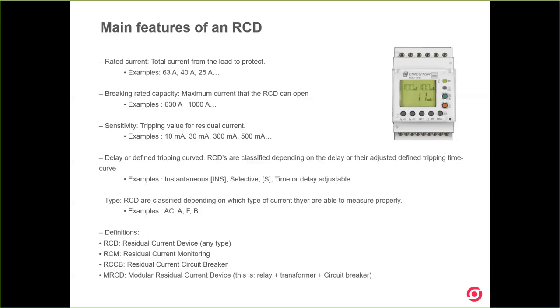Let's follow with the next concept: sensitivity. This is the tripping value for the residual current device. Probably you already know the most typical example, which is 30 milliamps. These 30 milliamps are very important because this value is the maximum current allowed to pass through the human body without any kind of damage. So this value is for protecting people — very important.